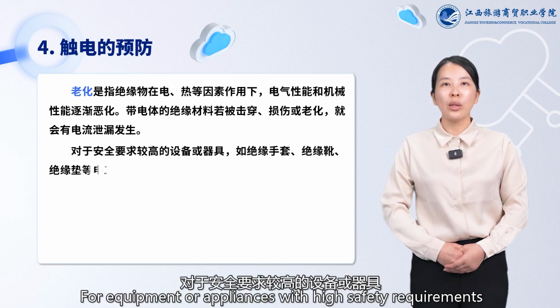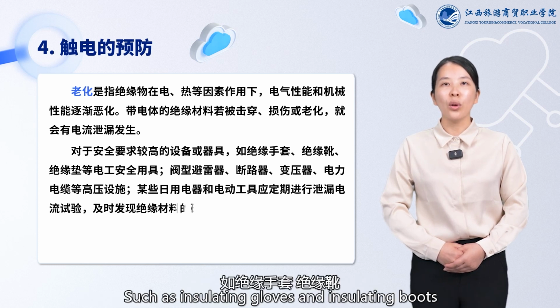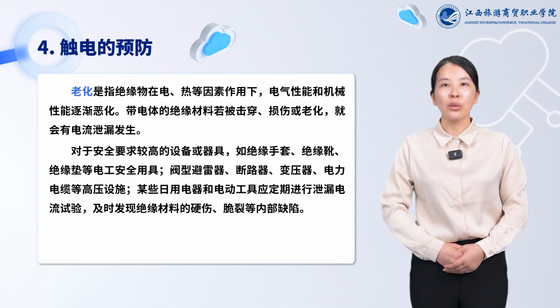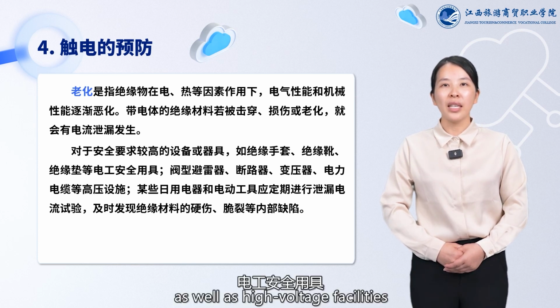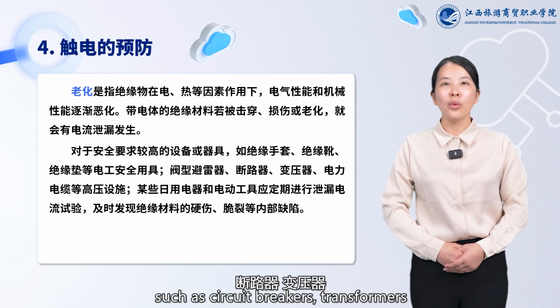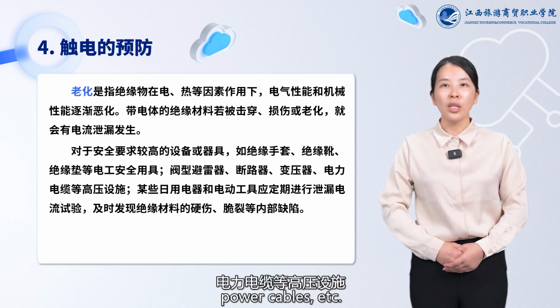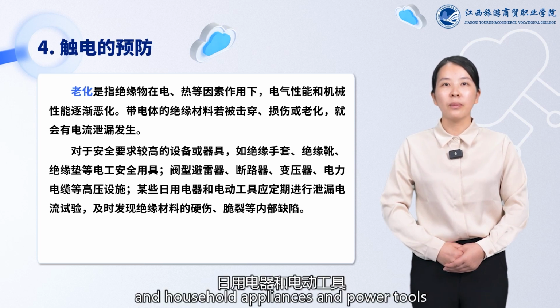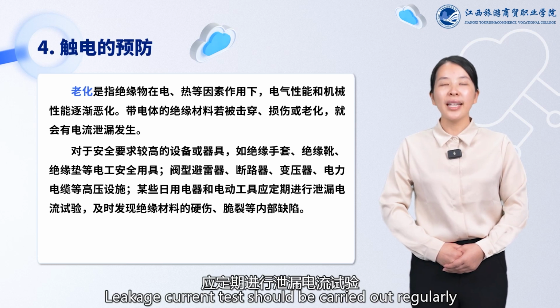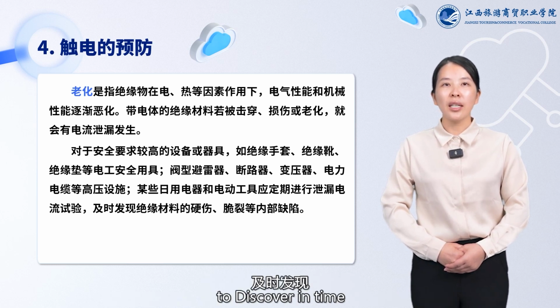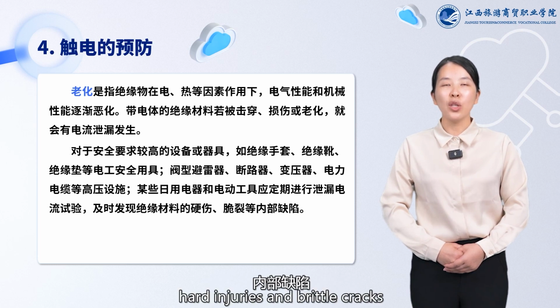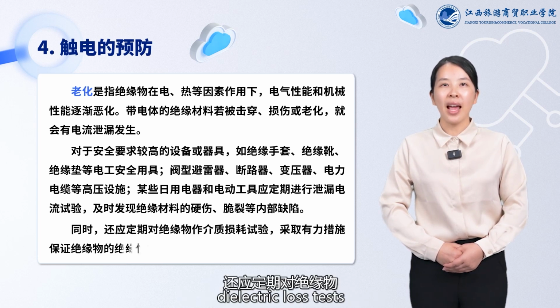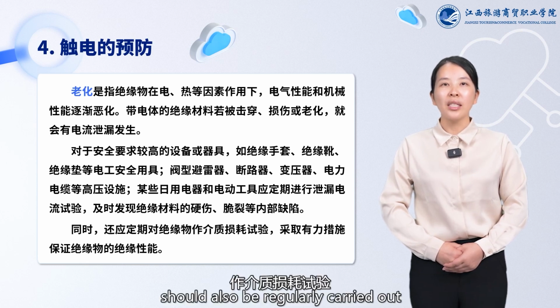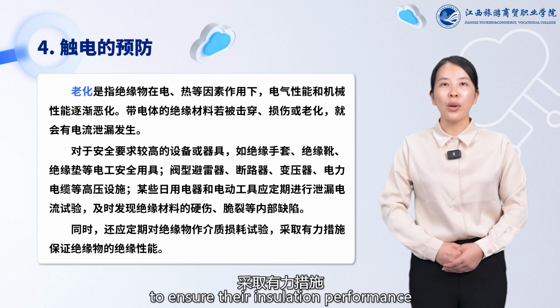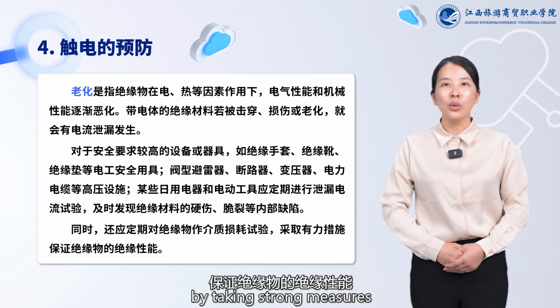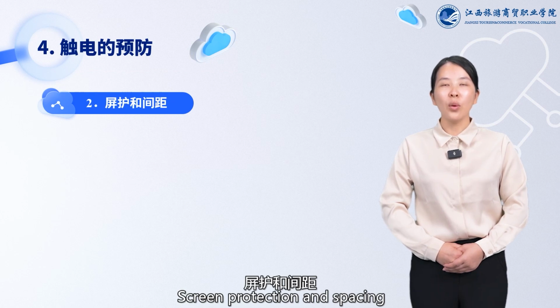For equipment or appliances with high safety requirements, such as insulating gloves and insulating boots, insulating pads, etc., as well as high voltage facilities, such as circuit breakers, transformers, power cables, etc., and household appliances and power tools. Leakage current tests should be carried out regularly to discover in time internal defects like hard injuries, brittle cracks, and meanwhile, dielectric loss test should also be regularly carried out on insulating materials to ensure their insulation performance by taking strong measures. Screen protection and spacing.